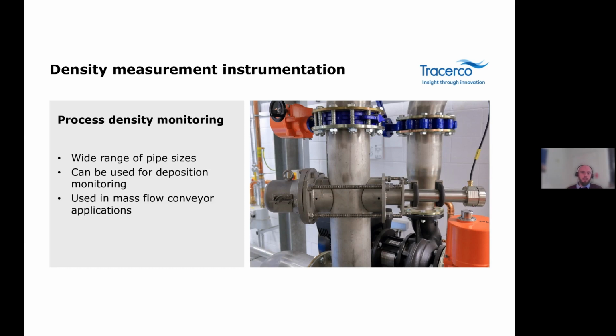Each system is designed to match the process and vessel information provided, and the source that is used is sized appropriately with the lowest size feasible, which will match the regulations for the region that it's going into. The output can be used for deposition monitoring, and this is done by measuring the density on the count rates. As the density appears to increase, this would suggest a change in deposition. It's also been used in mass flow and conveyor applications.